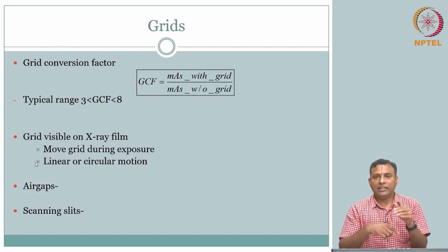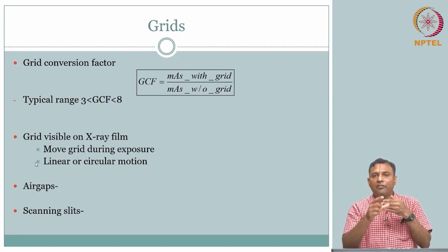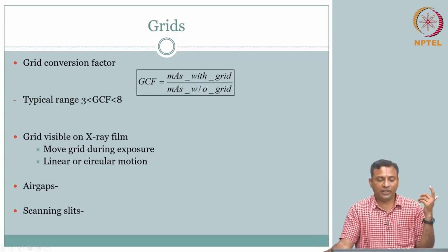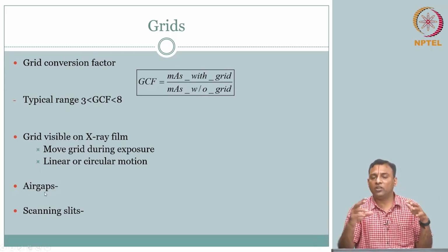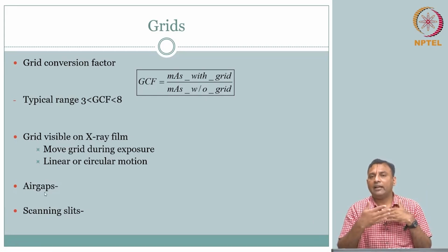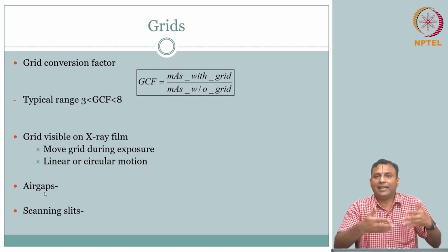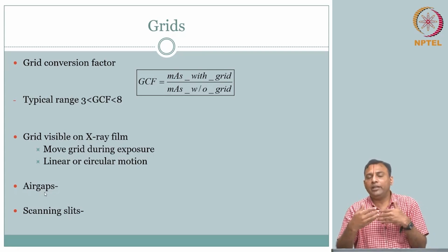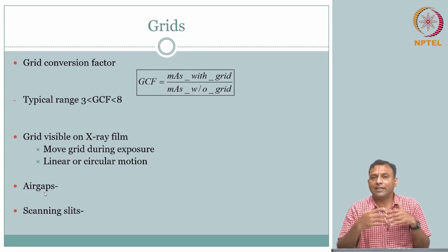So in some sense, if the detector is moved away from the object, then we could separate out these two angles. Okay, so in some sense it is not really an instrumentation. The idea is to exploit this knowledge that if you have a gap between the detector and the object, basically an air gap, you naturally reduce the Compton scattering.